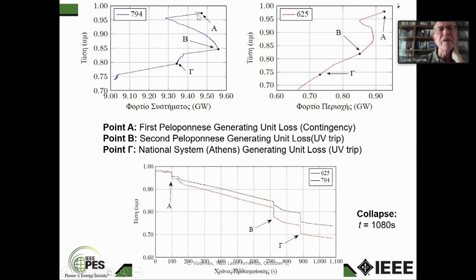system PV curve. So you see at point A, we have the unit loss. You see it decreases both the voltage and the consumption, because a decrease of voltage creates a decrease of consumption. You see that with the load ramp, you can increase the consumption above the initial point, which means the total system looks like stable. It can withstand its demand. But then at point B, we have a second generator loss because of under voltage. This is an under voltage trip, after which things become very, very messy.